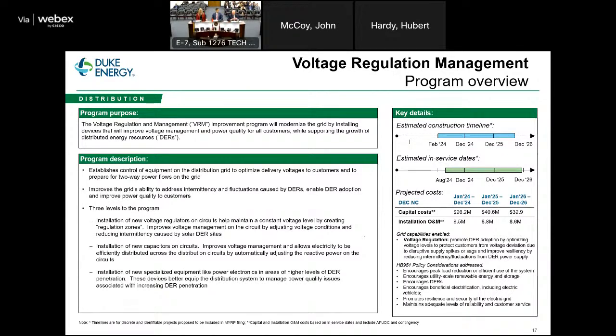Regulators and capacitors are not new, but the quantity and upgraded controls for two-way power flow are new. Power electronics are a new technology and provide instantaneous voltage regulation or reactive power support. You can think of voltage regulators and capacitors as the coarse adjustments when we need to make changes on a circuit, and the power electronics as a fine and instantaneous adjustment as needed.